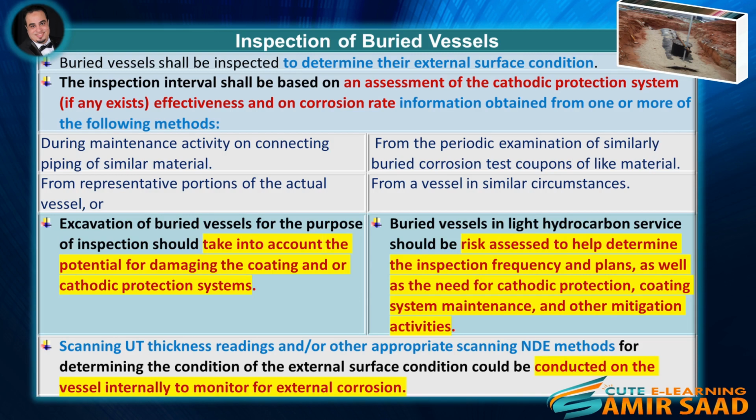Excavation of buried vessels for the purpose of inspection should take into account the potential for damaging the coating and/or cathodic protection systems. Buried vessels in light hydrocarbon service should be risk assessed to help determine the inspection frequency and plans, as well as the need for cathodic protection, coating system maintenance, and other mitigation activities.